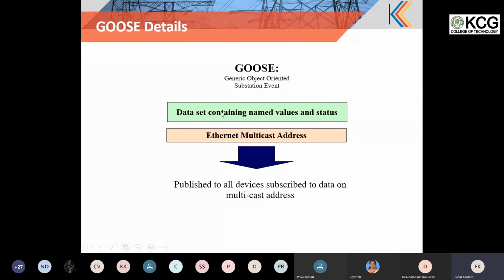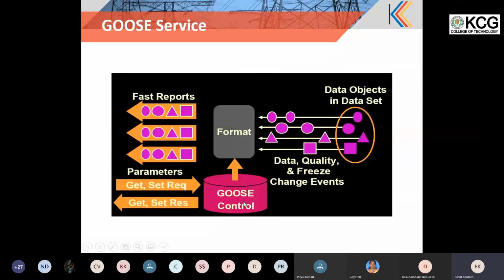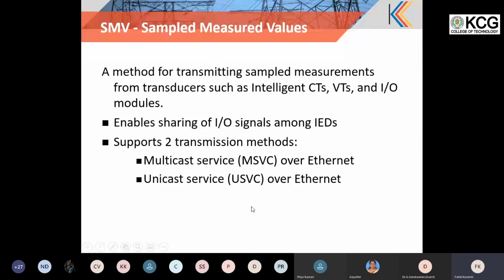So GOOSE again, there is a GOOSE control block, a data set associated with it, and there are trigger conditions. Based upon that, a snapshot is taken, and the current snapshot is sent out as GOOSE onto the network. Then set and get parameters are there, which can be operated over the GOOSE control block to change the data set, data element, everything can be achieved using the GOOSE control block. Sampled value is nothing but a fast transmission of the sampled measurements from the CTs, VTs or intelligent IO modules to the bay side, and it is a continuous transmission. It is again a multicast service over the Ethernet or a unicast service over the Ethernet that is used to send the data out.